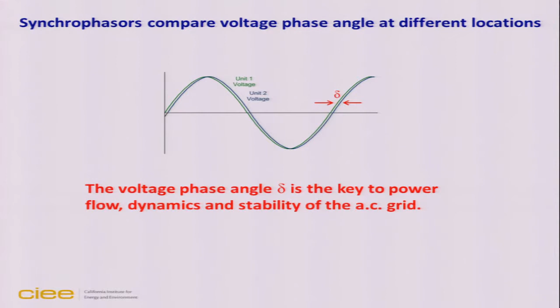This is your diagnostic key. In the past, it was never possible to empirically measure that little delta because to do it, you need a time reference. It doesn't mean anything to measure the voltage phase angle at one location at 3 o'clock if you don't know exactly what time it is at another place where you're also measuring that voltage, right? So you need to have these very precisely time-stamped measurements down to on the order of microseconds to compare them. And this really became possible in the late 1980s when the first synchrophasors were developed and implemented.